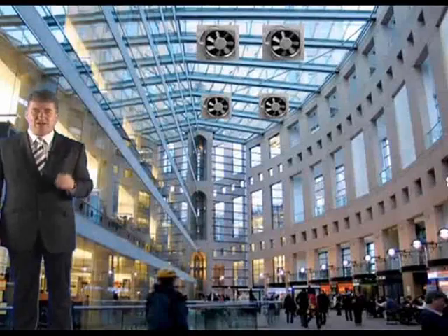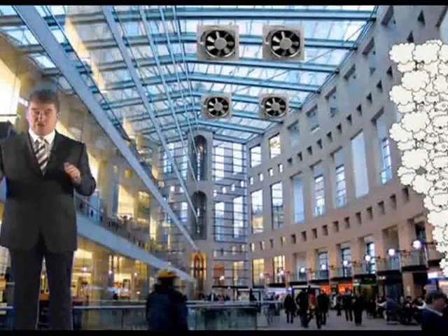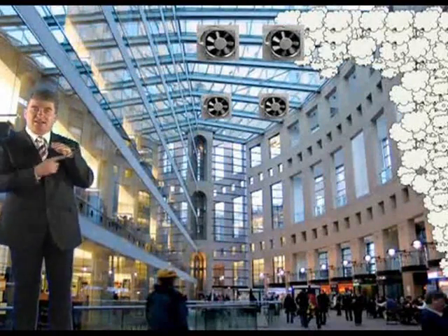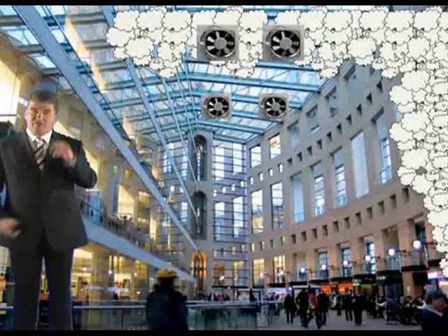The ideal option is to install smoke control, in other words, a smoke heat ventilation system, in every single shop. Now, this is very expensive and it's difficult to achieve. However, it's sometimes the only option. For example, some shops could have a small ceiling height, say 3 metres, where you can't let the smoke go down, so you've got a slot extractor, you've got to extract it, and it comes out of the shop. Sometimes you've got no choice. Generally, it's more practical to allow the smoke to enter the main mall and extract it there. So let it come out of the shop and then extract it.